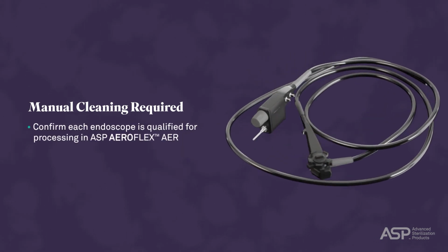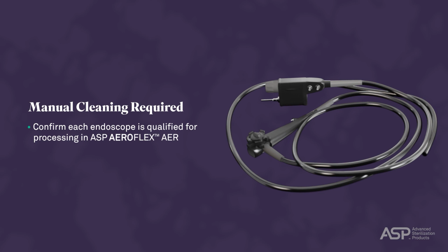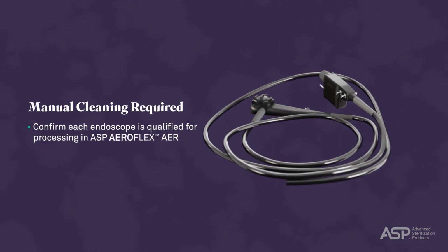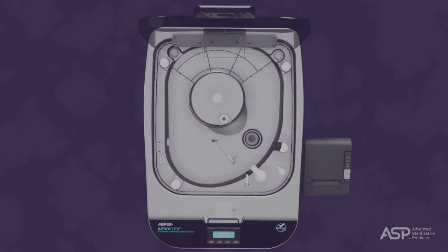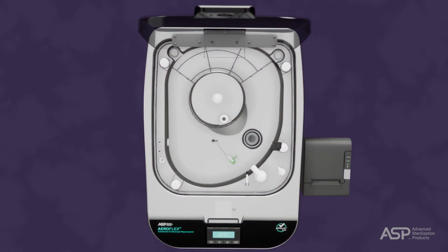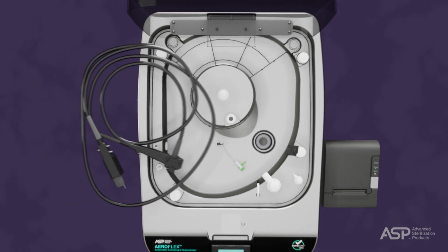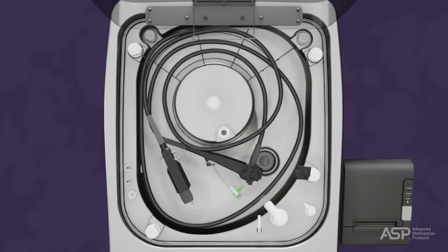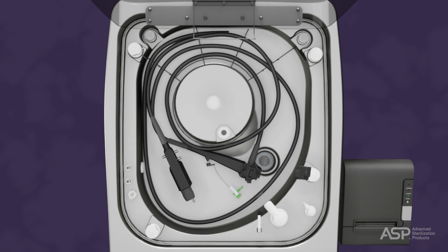Always check with your ASP representative to confirm each endoscope is qualified for processing in ASP AEROFLEX AER. When cleaning is complete, the endoscope is ready for loading into the AER as follows.